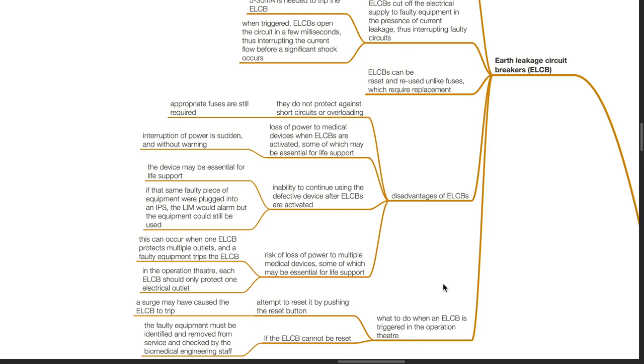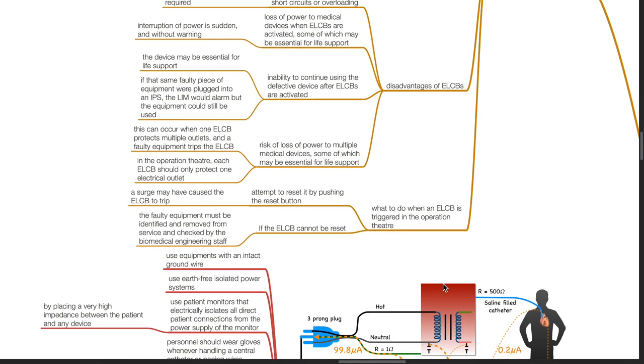Therefore in the operation theater, each ELCB should only protect one electrical outlet and should not be daisy-chained. What to do when an ELCB is triggered in the operation theater? First attempt to reset it by pushing the reset button; a surge may have caused the ELCB to trip. If the ELCB cannot be reset, the faulty equipment must be identified and removed from service and checked by the biomedical engineering staff.